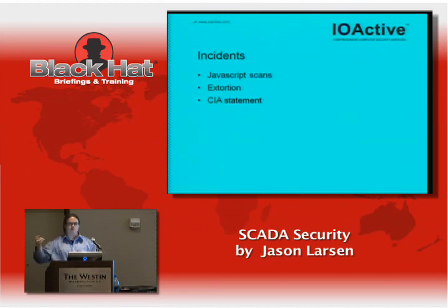What happened is also with all the embedded controllers we have there, to make them really, really easy to configure and nice to work with, we've taken all of the nice little embedded controllers and we put web servers on them. So if you have your PLCs out there right now, a lot of times you can browse to them to show up a nice graphical display of all the cards that are in them. You can drill down, you can see the points. Sometimes you can play with the points, you can reset it. It's all really easy to use. What's happened in some of those, the web servers really aren't that industrial strength. So people just go out to dancingbears.com, get back a bunch of JavaScript port scanning code in their web browser, and that comes over there, starts scanning through the RFC address range. It finds the embedded controllers, sends a whole bunch of JavaScript to it to try and attack it, and the web server turns over and takes out the process along with it.